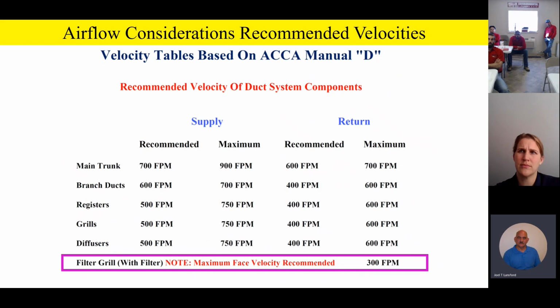And if we follow these Manual D recommendations when we do our airflow and duct design, it'll keep us out of trouble. So I always recommend looking at those things when you're putting one of these in, and make sure your ductwork's in good shape and you've got the proper airflow, because it really can affect a modulating system more than a regular non-modulating system.